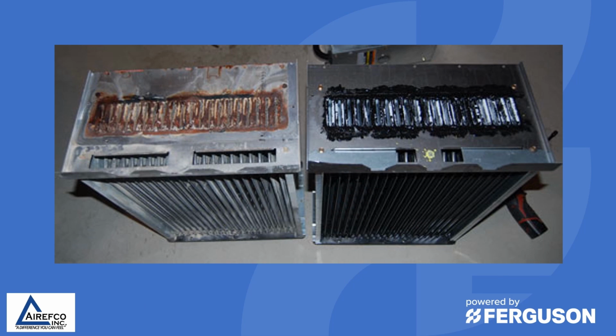Technicians need to be aware of what a good heat exchanger looks like compared to one that is defective. This heat exchanger on the right is out of the box and is brand new, and it has the black coating that they use to seal the panels into the front plate of the heat exchanger. Many times this coating can also restrict the flow through the heat exchanger, so when you are changing a heat exchanger, make sure you double check that the coating is not restricting the air through the panels.